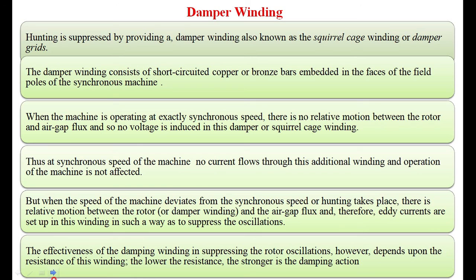The suppressing capacity depends upon the resistance of the winding — the lower the resistance, the stronger the damping action. These damper windings play an important role when there is an oscillation in the rotor: a voltage is induced in the damper winding, producing a damping torque which opposes the oscillation, so that ultimately the rotor settles down to the new operating point.